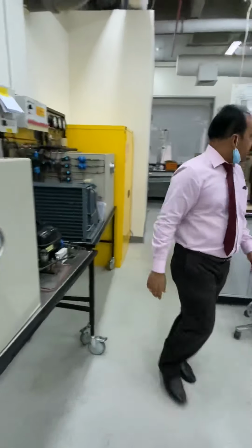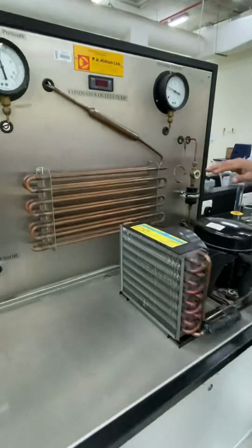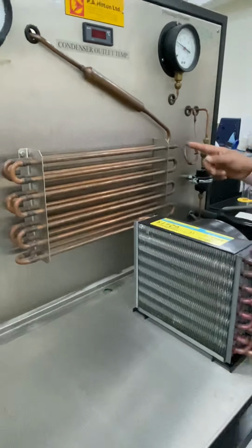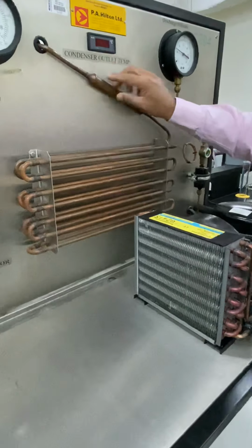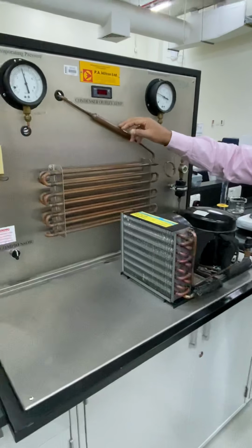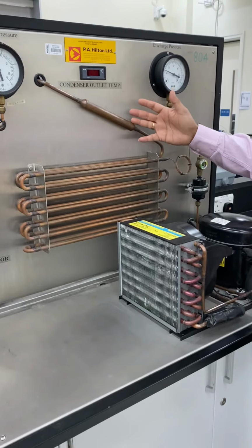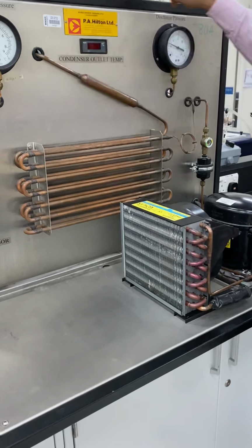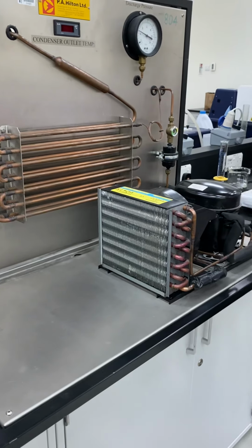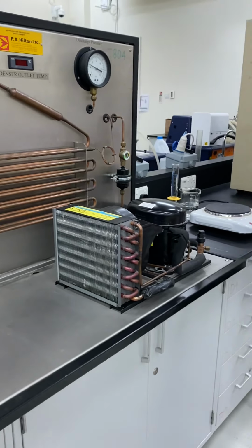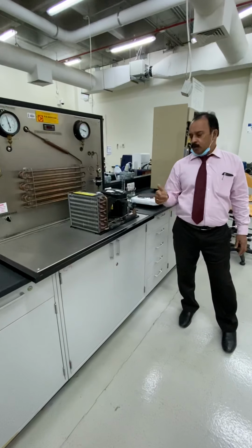And then coming to here, this is the evaporator. From the condenser, you go to the expansion valve, this is the capillary, and then here this is the evaporator. From the evaporator, this line is the low pressure gas. The liquid refrigerant becomes low pressure gas refrigerant, and it goes back to the compressor again. So this is another evaporator. The function of the evaporator is to absorb heat and change the phase from liquid to low pressure gas refrigerant, and then return back to the compressor.